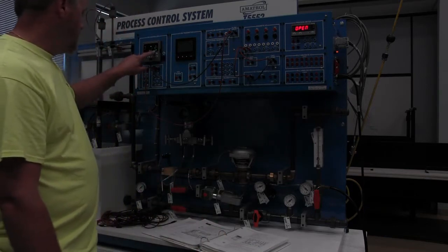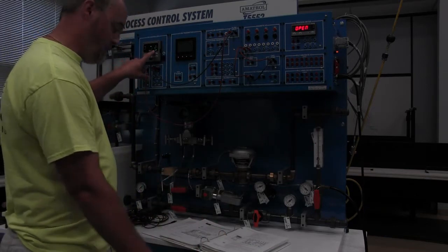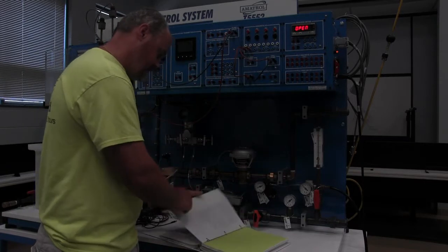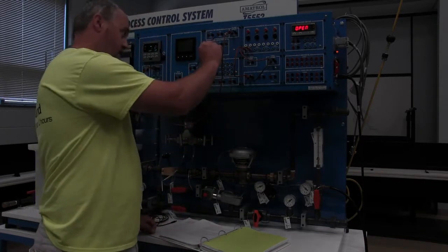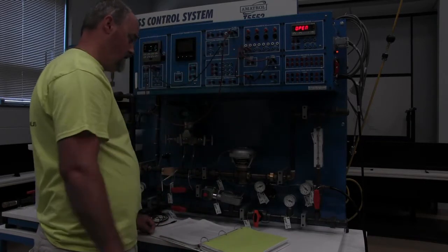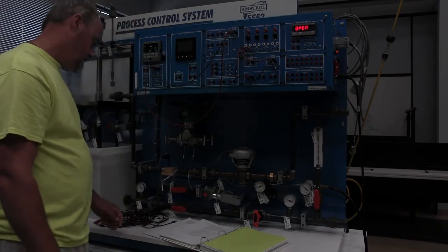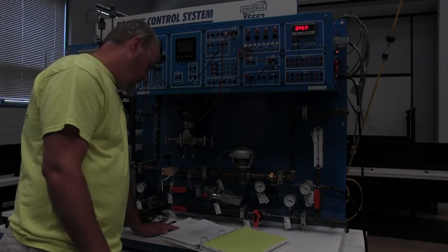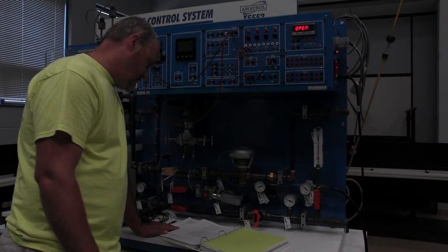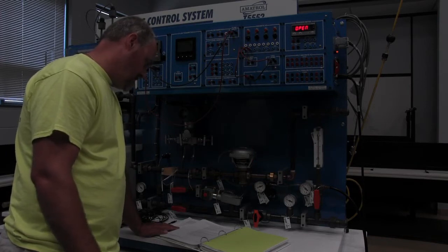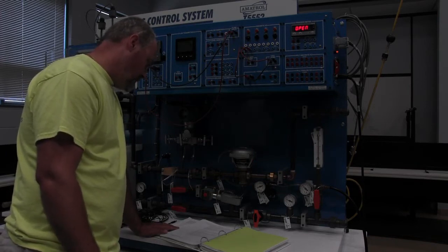We want output on the bottom, which is 0 right now. We're going to turn the selector switch on for the pump. When the level increases to the 2-inch mark in the tank sight scale, adjust the output from the controller using the up and down arrow keys to stabilize it at 2 inches.